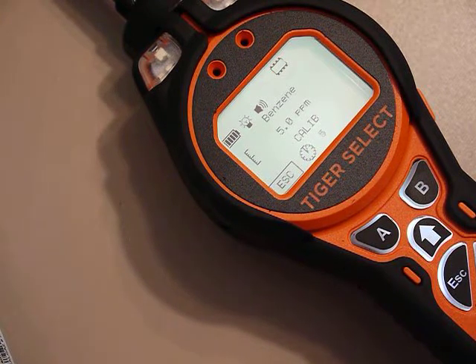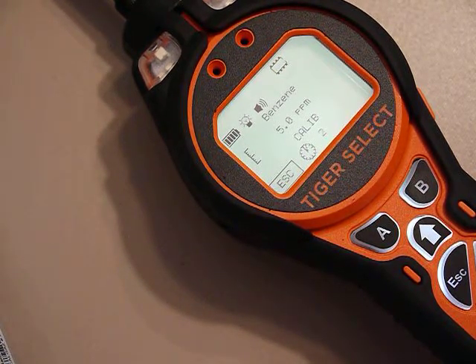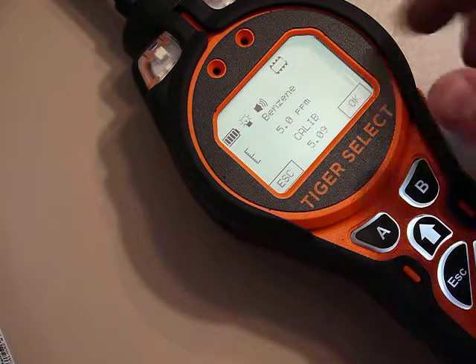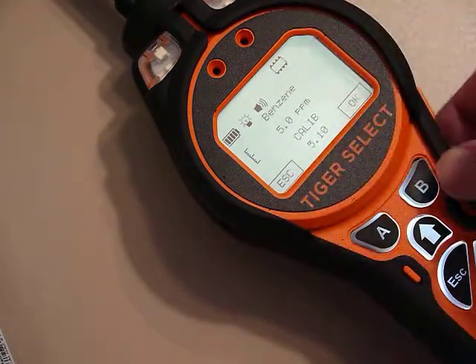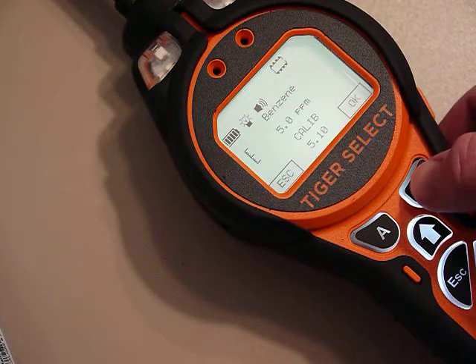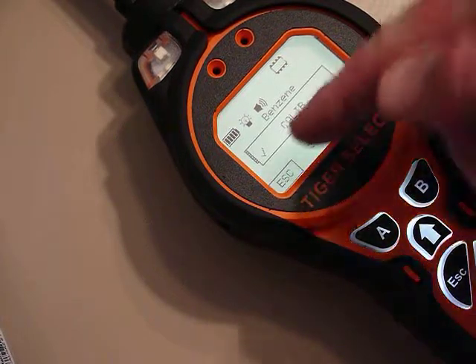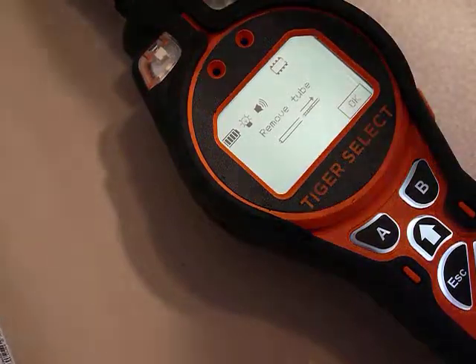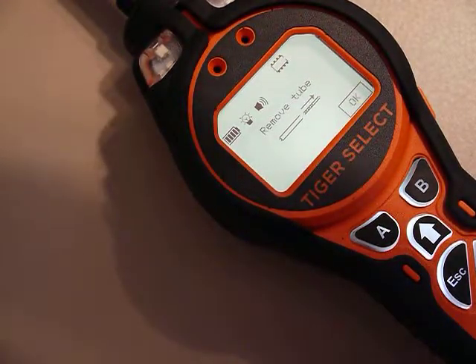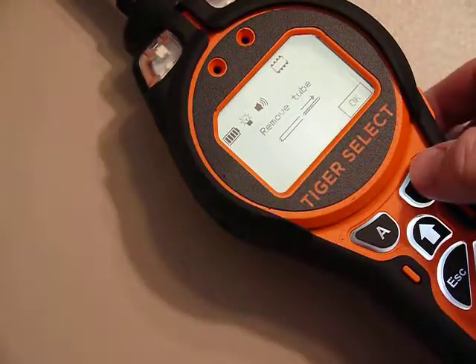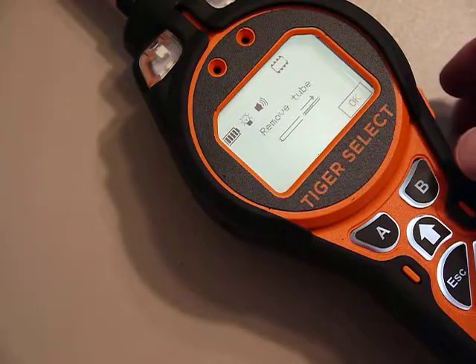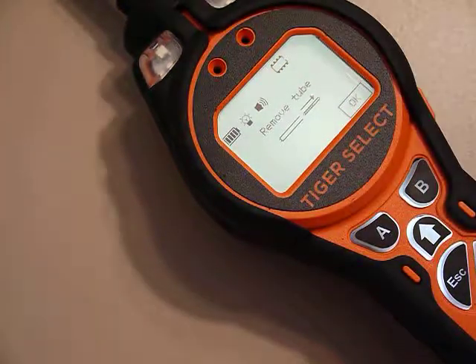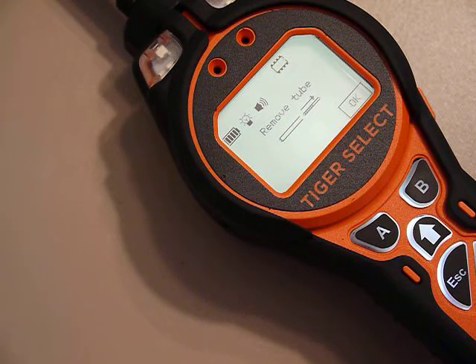Okay, it's almost done. Okay, it's doing a good measurement there, and I hit OK. And the calibration says there's a check mark, and I'm ready to go. So I can shut off the gas now, and you should watch the next video. It'll show you how to go out and actually take a sample now and get a direct benzene measurement.